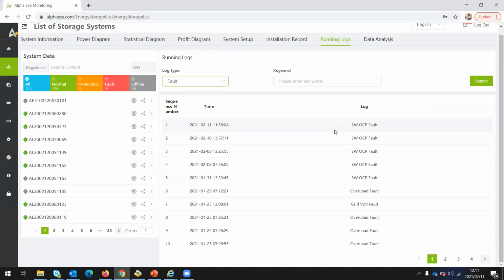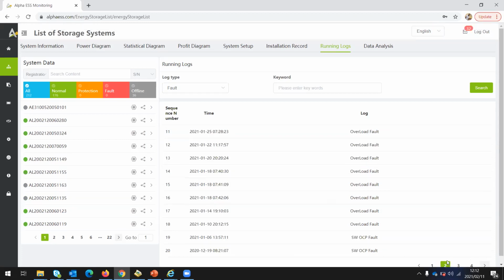Basically, an OCP fault means the battery was overloaded during that time. One of the batteries had too much power drawn from it, and then it gave that fault. So you get all the faults logged for different times, and that helps you troubleshoot. You can just scroll to check all the different types of faults that happened to the system, so that whenever you are going to site, you are already trying to find the solution in your mind. So basically that's much of it in terms of the monitoring portal.